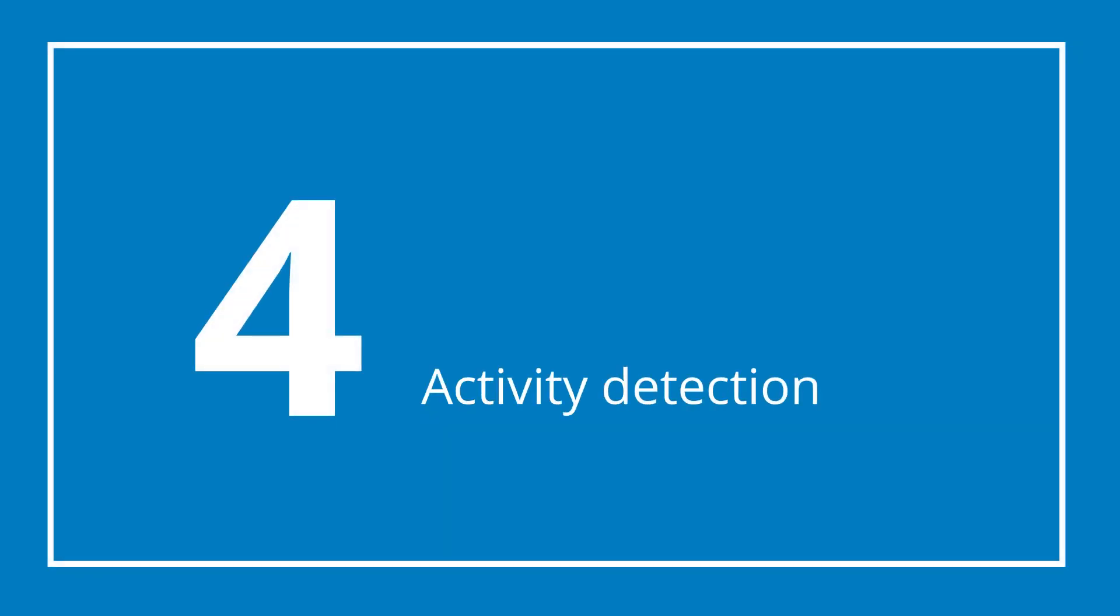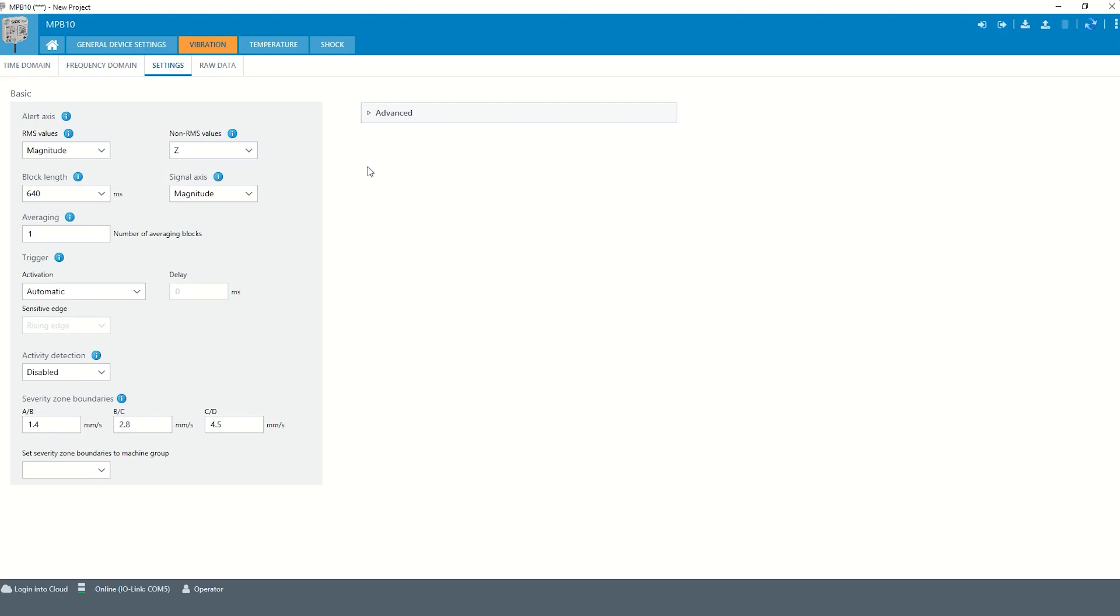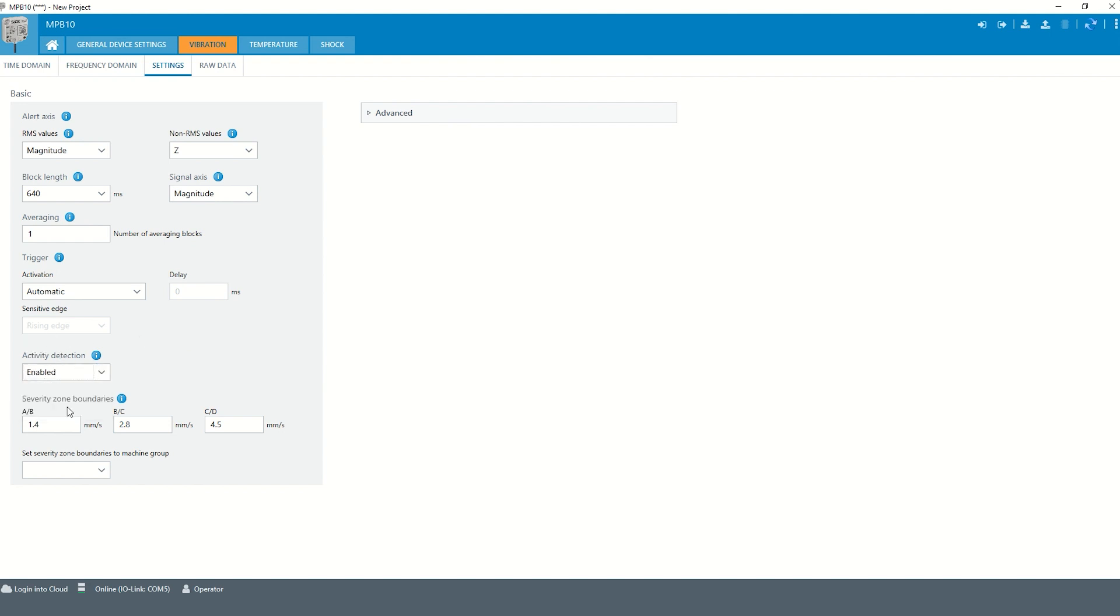Chapter 4: Activity detection. The activity detection allows the sensor to only update the key values if a vibration is detected. This avoids that the key values are calculated from this noise signal. The activity detection can be enabled in the vibration settings.